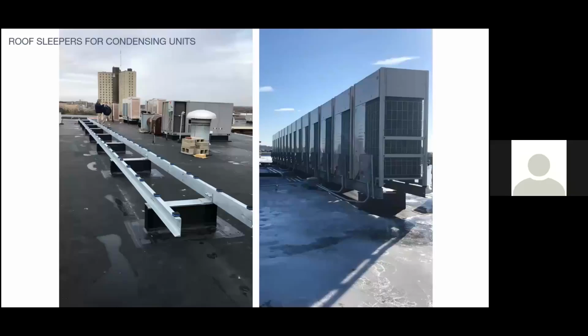Now, looking at the condenser units on the roof, we always suggest elevating the units at least 18 inches off the ground, like Jason mentioned, in our climate to just keep them above the snow line. So there are a few different options to do that. One being just off-the-shelf stands, which you might have seen before, that need to be bolted into the roof. So these come in set sizes that are to fit each different manufacturer's condenser unit.